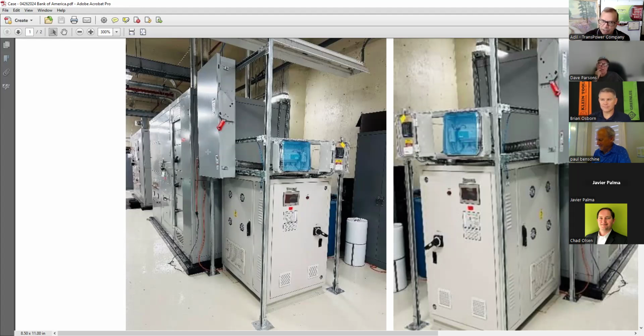So the reason why the inspector wants this is he's thinking, so far in the last 15 years, you have never removed an MPTS. No, I shouldn't say that. There is a case where we did remove it. But very rarely, once you install an MPTS, you never remove it and take it away. But the inspector says, if you want to remove an MPTS, you've got power here coming into this MPTS. How are you going to remove it if you don't shut the power off to the MPTS? That's why this disconnect switch or an MCCB in the switchgear is very important from the inspector's point of view.